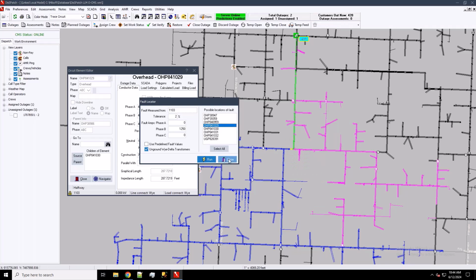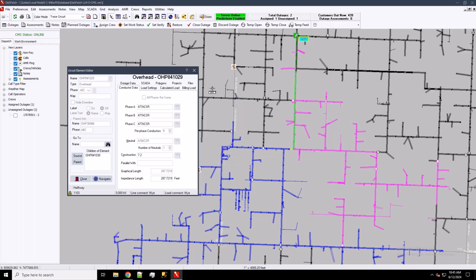We've had customers give us great feedback on the accuracy of the fault locator tool and the results it provides. But of course, that is all dependent on their detailed circuit model being established in GIS correctly. We've got to have those correct definitions for each conductor. We've got to have the correct impedance values. We've got to have all that data underlying the system for this to work correctly. But we'll assume our crew gets out there.